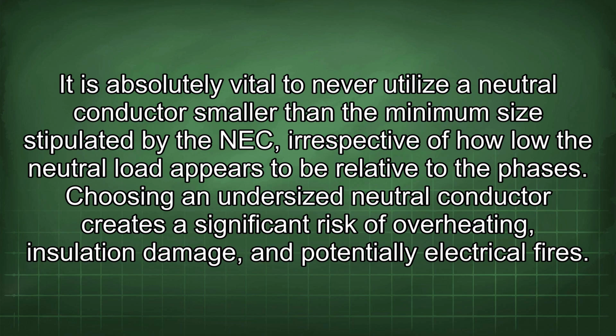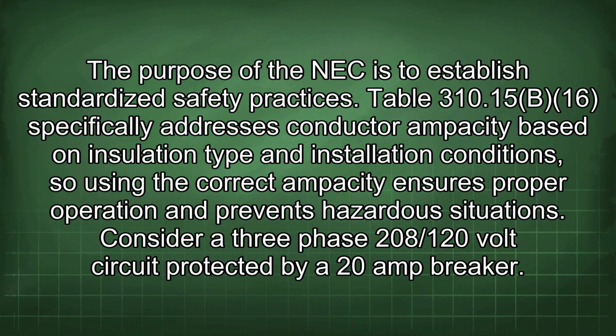Choosing an undersized neutral conductor creates a significant risk of overheating, insulation damage, and potentially electrical fires. The purpose of the NEC is to establish standardized safety practices. Table 310.15(B)(16) specifically addresses conductor ampacity based on insulation type and installation conditions, so using the correct ampacity ensures proper operation and prevents hazardous situations.